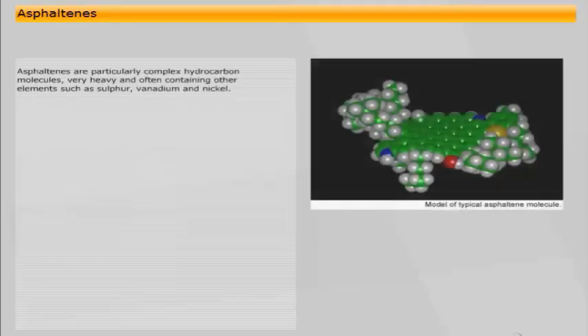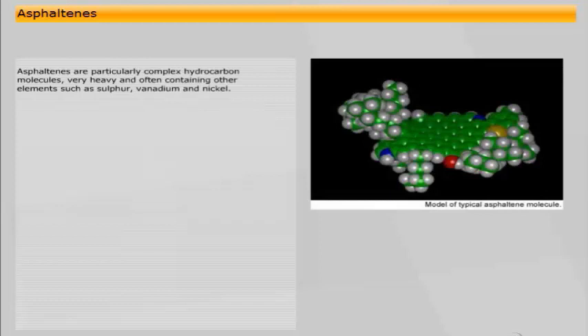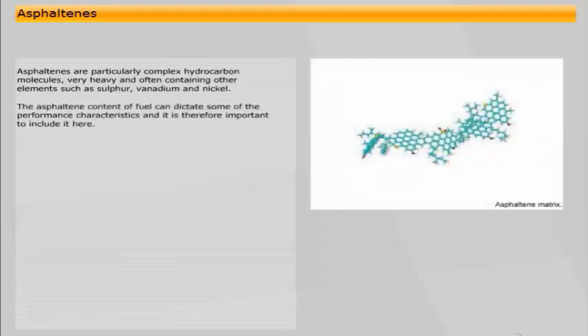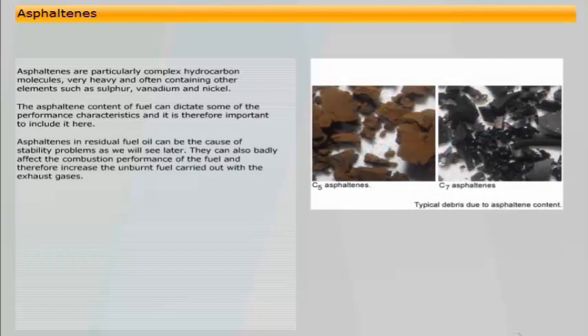Asphaltenes are particularly complex hydrocarbon molecules, very heavy and often containing other elements such as sulfur, vanadium and nickel. The asphaltene content of fuel can dictate some of the performance characteristics. Asphaltenes in residual fuel oil can be the cause of stability problems and can also badly affect the combustion performance of the fuel, therefore increasing the unburned fuel carried out with the exhaust gases.